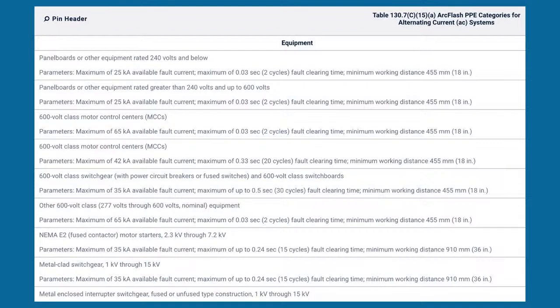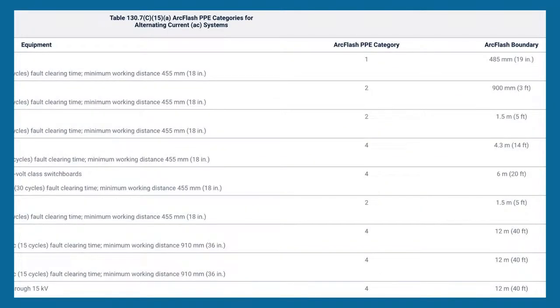Now, let's just look at a 600 volt motor control center, one right underneath it. It says a maximum of 65 kA available fault current. It's got a clearing time of 0.03 seconds or 2 cycles, and a minimum working distance of 18 inches. Now, come across. It tells you I'm still in a hazard risk category, but my arc flash boundary just increased to 5 foot. See? So you have to look at all of this. And this is where you get it.